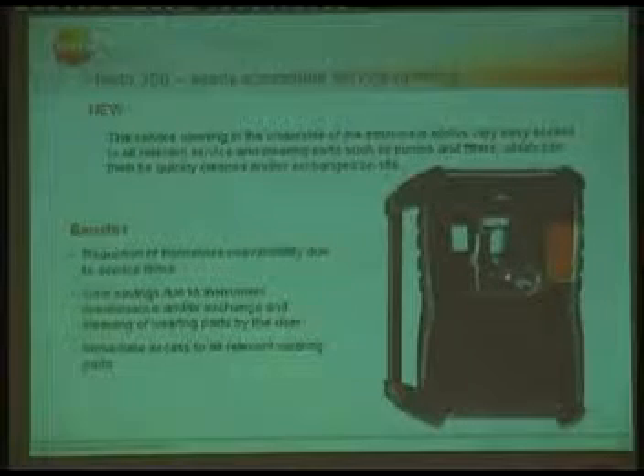Also, this one here, the very easy access to the service part I have shown before. And this helps, of course, cost saving because you can do basic maintenance work by yourself. You can clean or replace pumps by yourself. The same with the sensors. And this is just an example. Here we have also a small filter sitting between the gas preparation unit and the condensate trap. And all you have to do is just removing the condensate trap, and then you have very easy access to this filter here, which can be replaced by yourself.